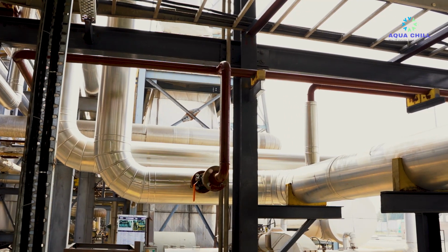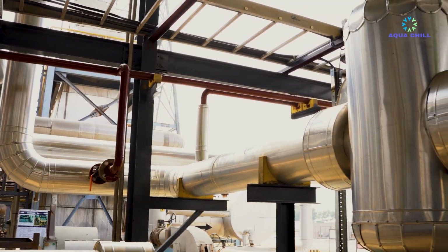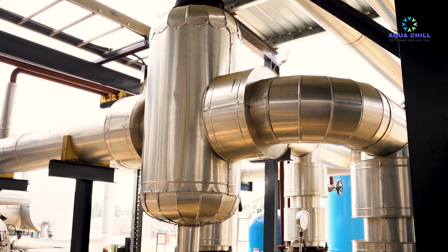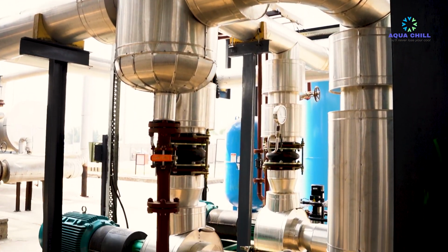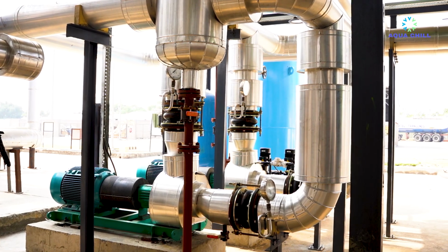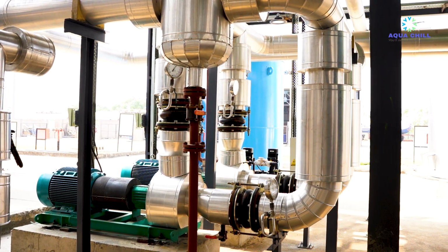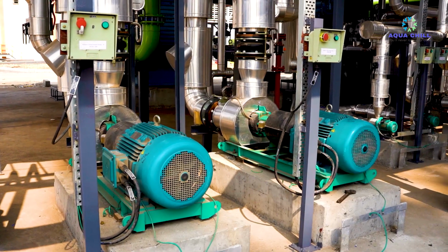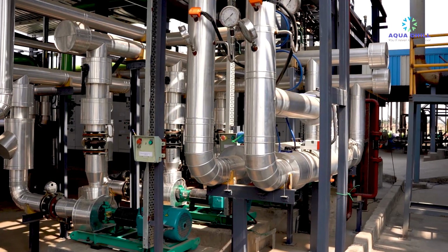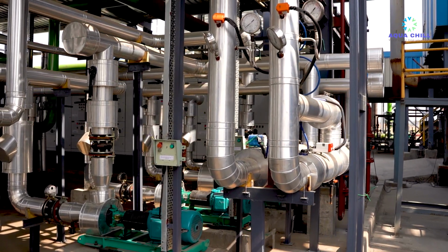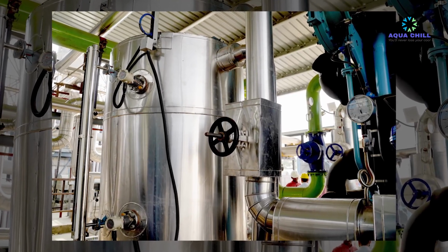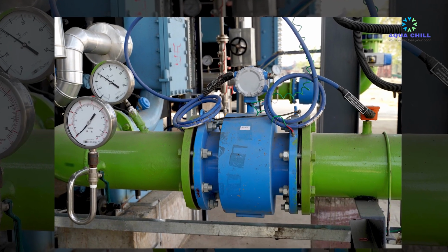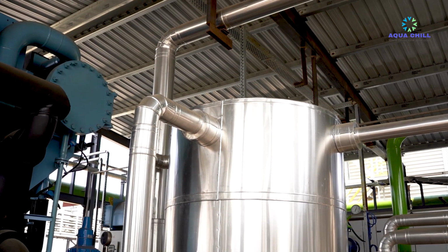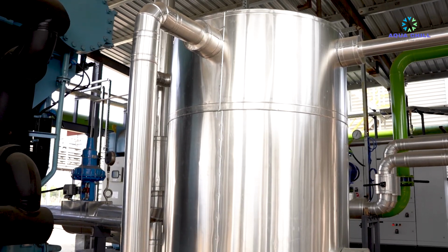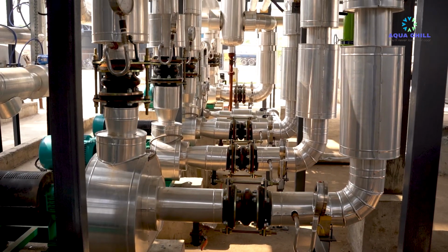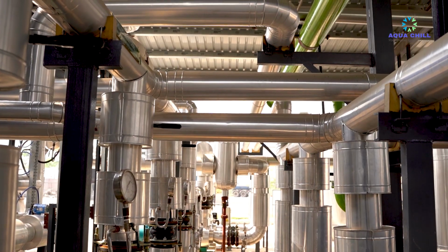Another challenge was to achieve fluid dynamic properties. There was this limitation of adding any pressure drop in the intake part of the process air compressor. There was also a huge risk associated with any suspended moisture particles getting carried to the compressor inlet. That would have led to a massive problem in the downside process. Immense efforts were given in doing detailed calculations and selecting the right cross-sectional area, a suitably sized heat exchanger followed by a unique combination of mist elimination and hydrophobic material filtration.